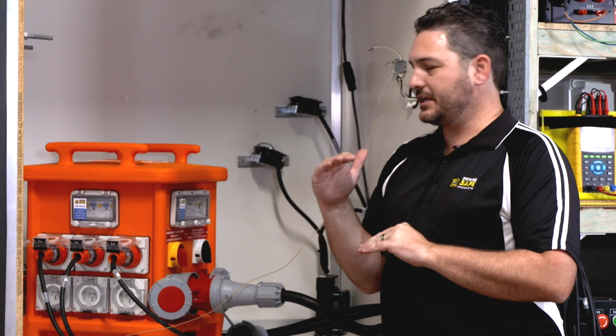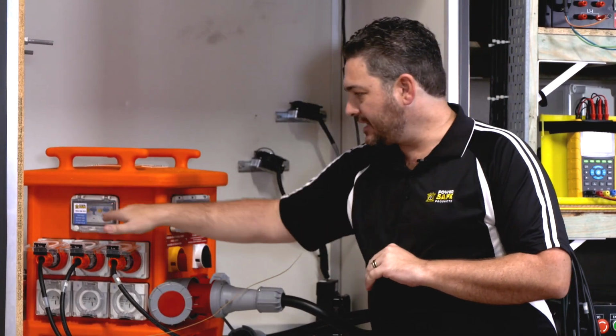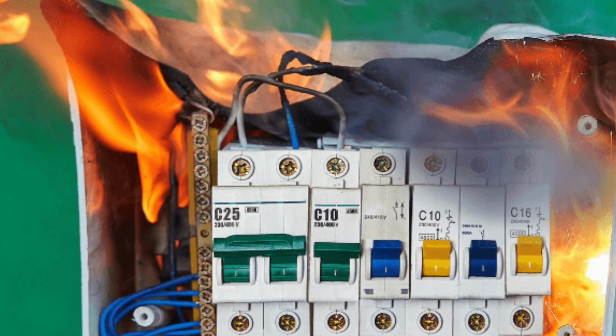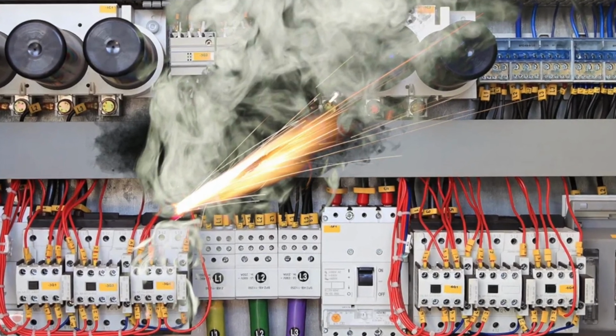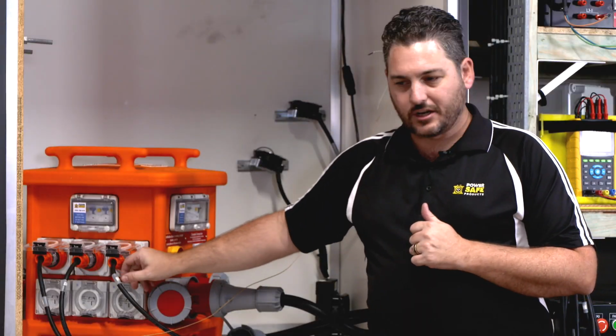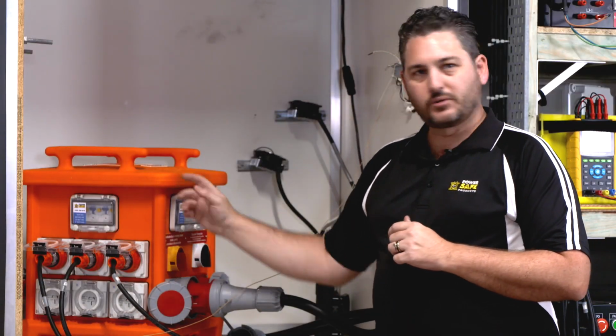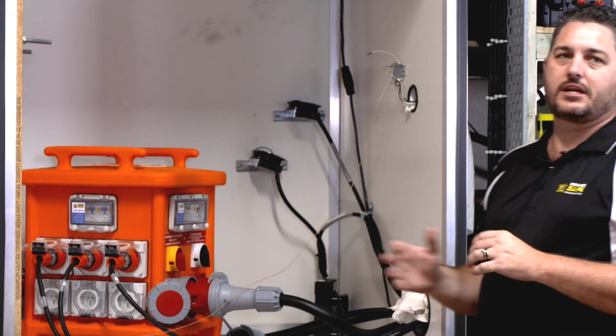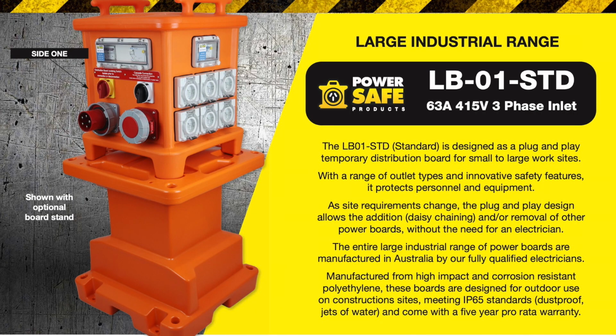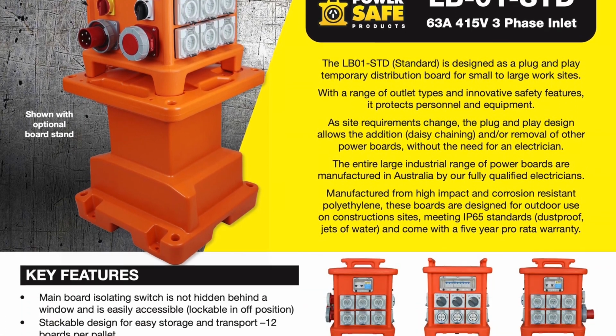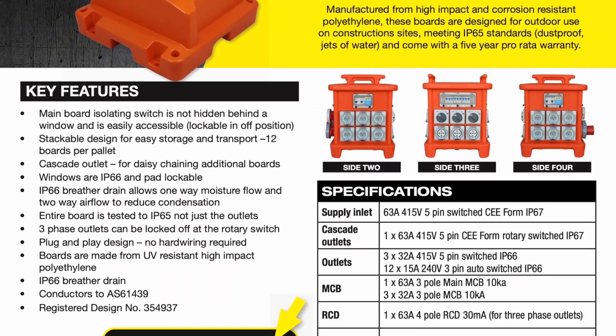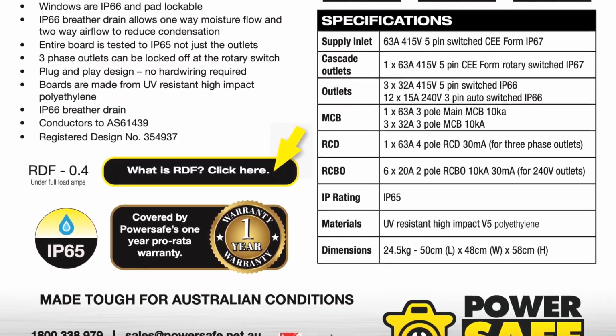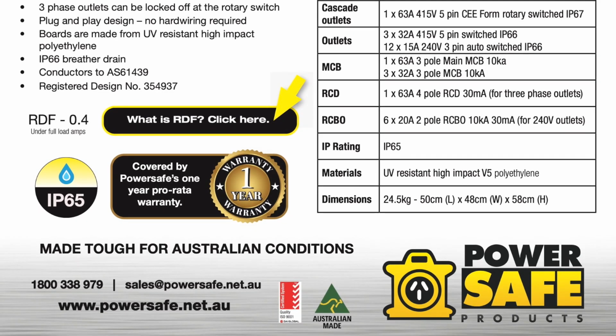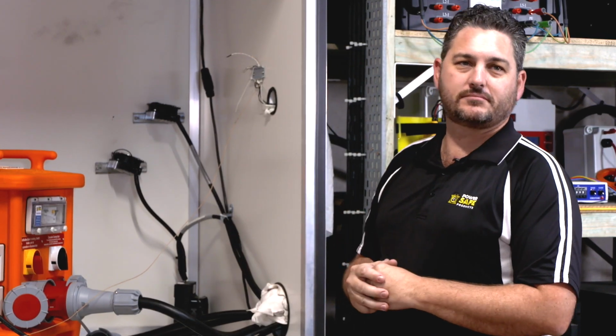If you do go over that temperature rating, you can start getting failures in this. You can get cables melting internally, which can lead to fires, can lead to arc flash, and damage any components that are plugged into it. So if you've got sensitive equipment plugged in, you'll get surges down the line and that can damage that equipment. So it's all about making sure you use the best quality components you can, the best internal components you can. It's all backed by those manufacturers as long as we stay within those temperature ranges, and this is how we prove it.